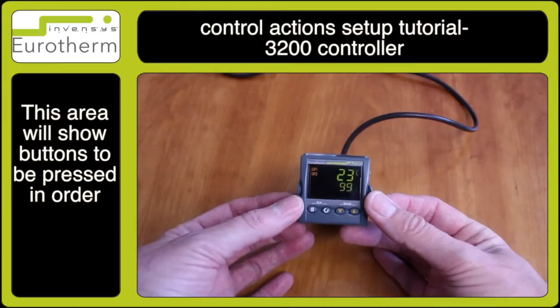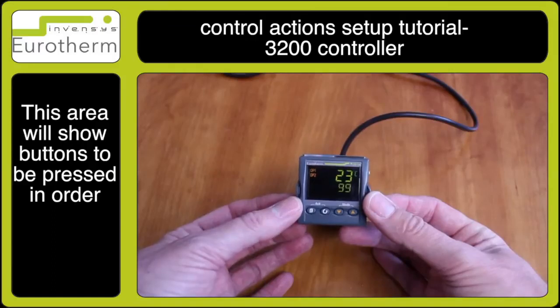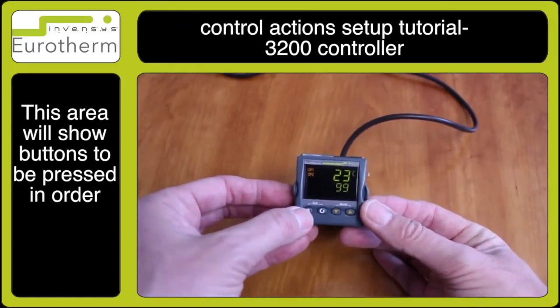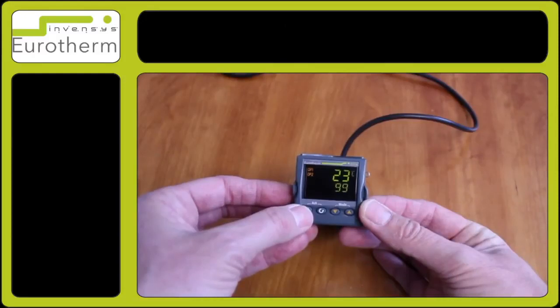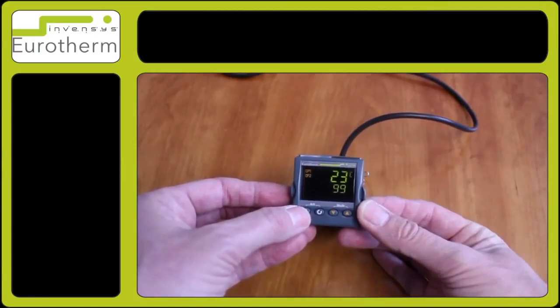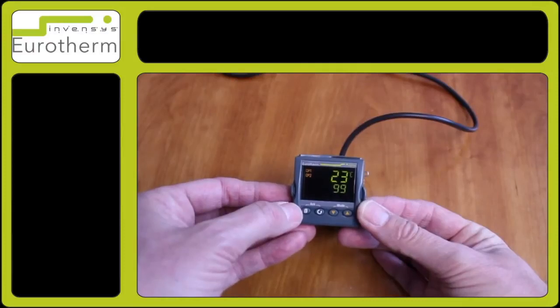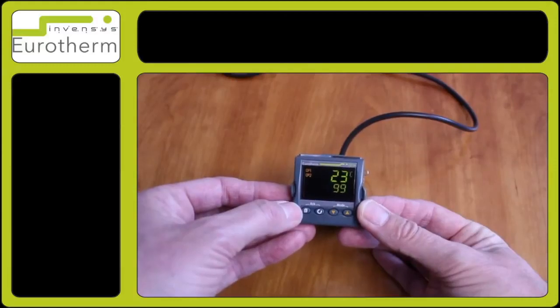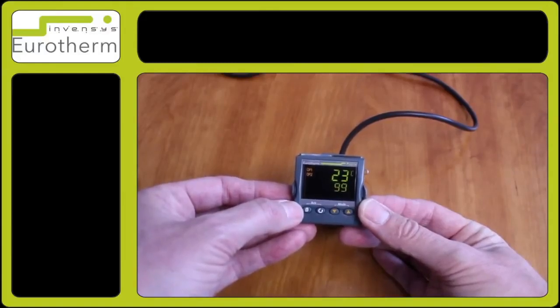In this demonstration, I will show how to set up the control action for a particular application. If you wish your instrument to produce an output when the set point is above the process variable, the temperature, you will need to use reverse acting control. If you require the output to be at 0 whilst the temperature is below the set point, then you will require direct acting.